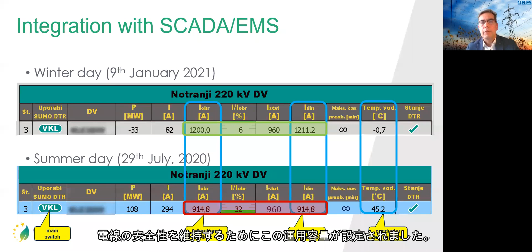This is important to understand how we use the low values that happen during the summer day. That day we calculated, for that particular moment, 914 amperes, which is below the static value, but this value went into operation as the operational limit to maintain the safety of operation of this power line. And yes, ELES is using conductor temperature measurements.